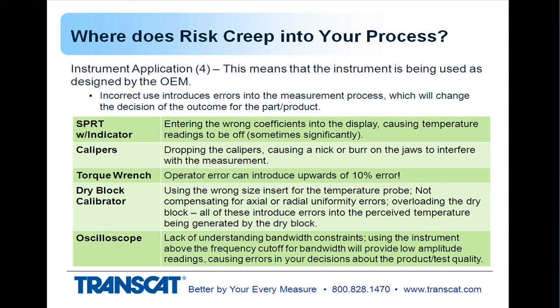The application, and that's what that leads to, is the correct use of the instrument. Incorrect use can introduce the errors that can cause you to have a different outcome of your decision whether the product's good or bad. A few examples here. If you have a platinum resistance thermometer with an indicator, the way that has to be used is that during the calibration there's a set of coefficients determined that have to be programmed into the display. There are some types of connectors where that's automatically programmed into the connector and it removes the operator error. Some of the older units have that, though, where you have to enter the coefficients into the display.